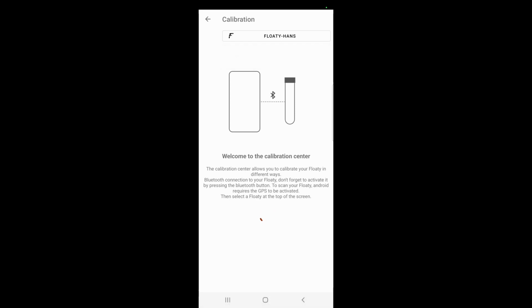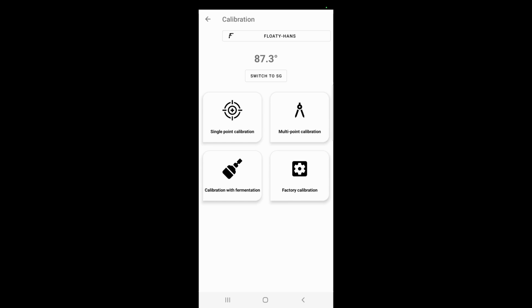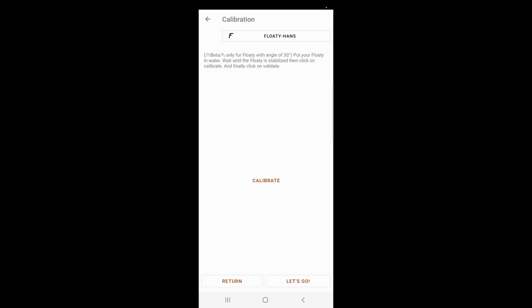Sometimes it decides it wants to not play nice. We'll touch the pin again, it turns the Bluetooth back on. So here's our calibration screen. The one that I'm going to use to start with is a single point calibration. And in order to accomplish the single point calibration, notice here it says beta only for Floaty with angle of 30 degrees. So we'll put the whole Floaty together and put it into the tube, and it will counterbalance it so that when you put it in water, it sits at 30 degrees.